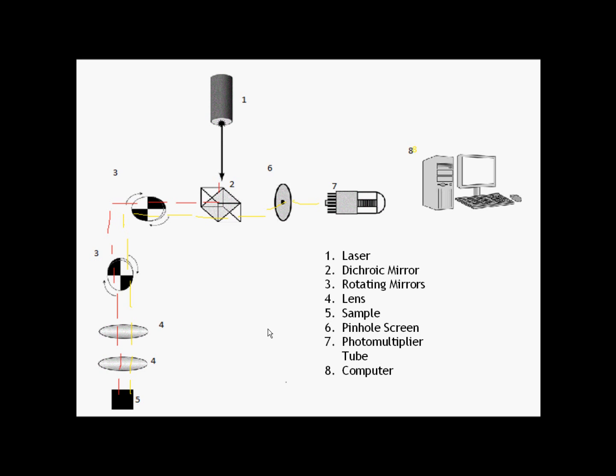The focal point of the second objective lens focuses light from the first objective lens's focal point, and the resulting wavelength passes through a screen with a pinhole or a slit depending on the microscope, so only the desired wavelengths are read from the sample. The light from the pinhole is measured by the photomultiplier tube. The incoming photons enter the tube's electrical field and bounce off the dynodes and the anodes to create a current that is read by a current meter, measuring the electrons collected at the anode and converting them to an electrical signal read by a computer.